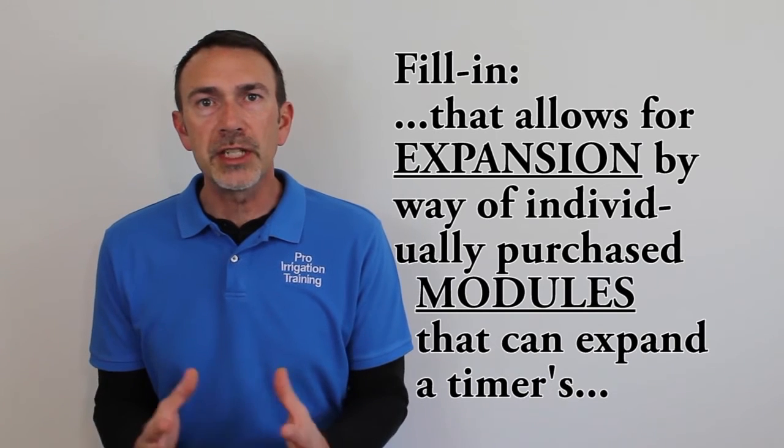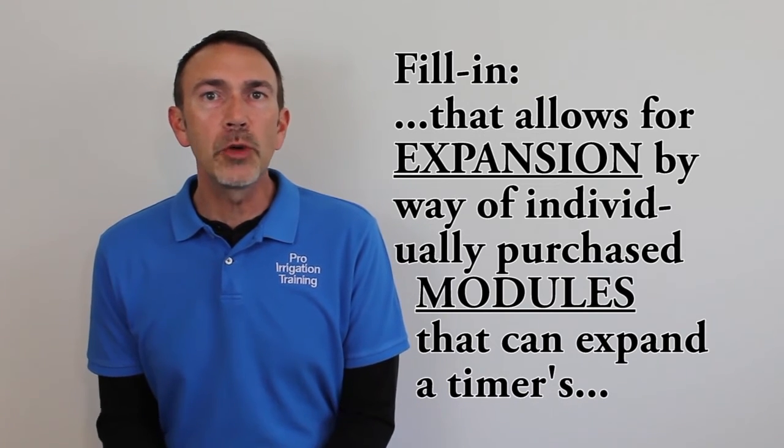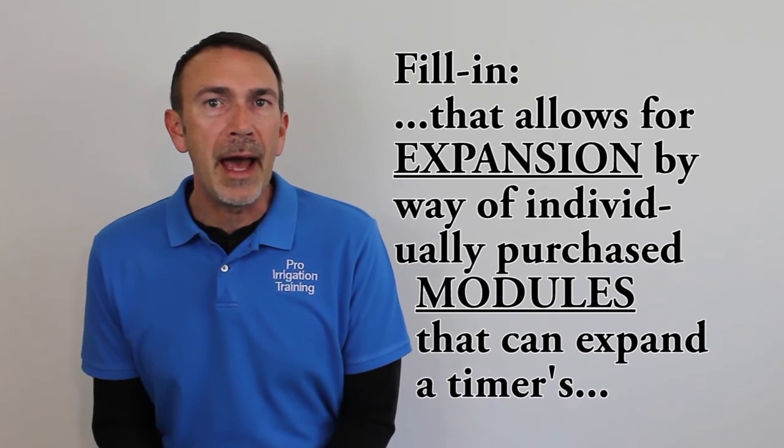Most manufacturers offer a modular version of their timers which allows for expansion of the number of zones by way of individually purchased modules that fit into the back of the timer. Usually these models come with one module in it and that'll have three or four zone terminals, a master valve and pump terminal, and also a terminal for your common wires. Usually these will expand by way of these individual modules up to 12, maybe 15 zones. Some of the larger timers have modules of 10 or 15 that can plug in for some of the larger properties or commercial properties that you might be dealing with.